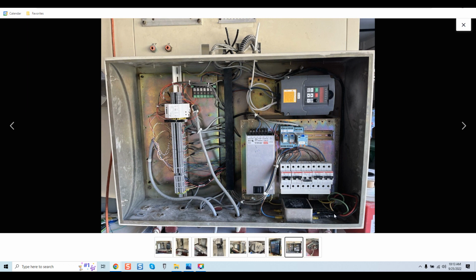Things down here that are slightly comical is the fact that I believe this is an EMI filter over here. I can't tell for sure. But he has electrical tape around these connections, guys. And you can see it right there. VFD being mounted in this enclosure.